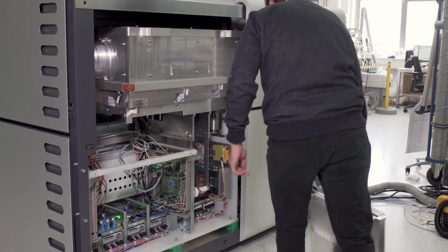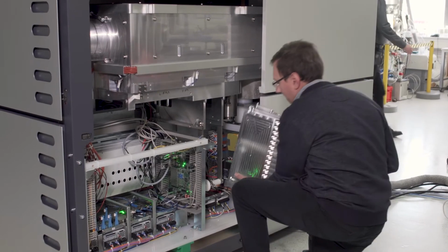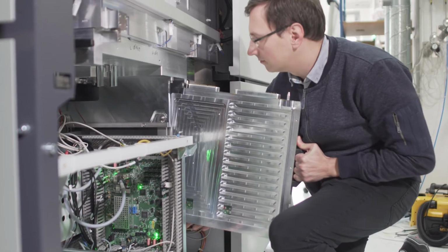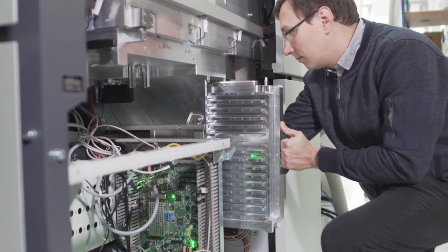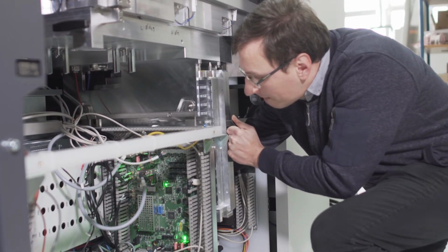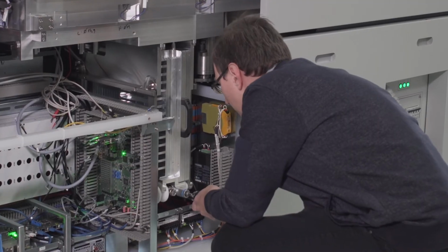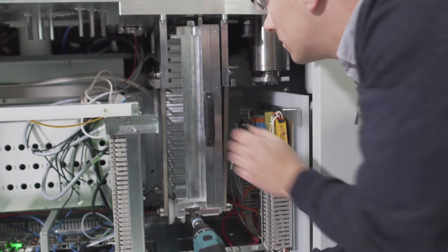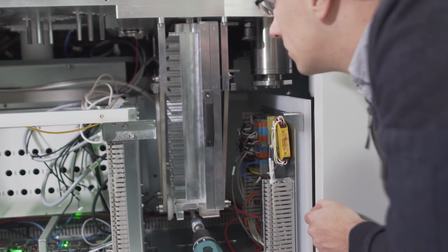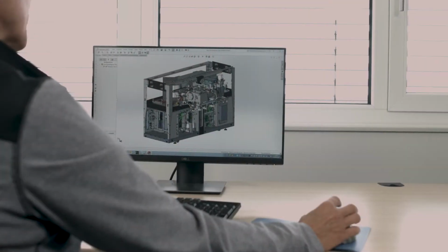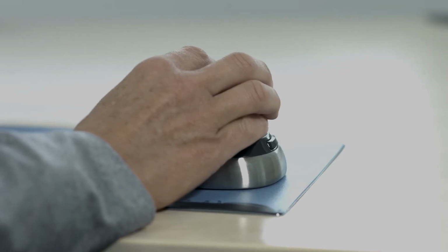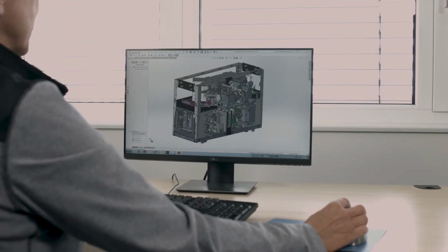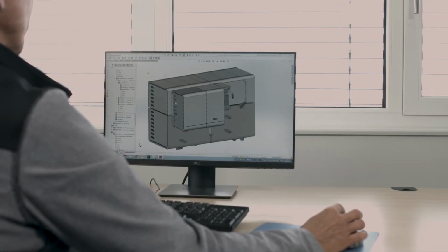The new ion current amplifier system allows the installation of 24 amplifier slots with automated gain calibration. It has a very compact design and is easy to service. Heated and maintained under vacuum, allowing lowest noise and highest stability. The new amplifier design incorporates an increased dynamic range and optimized time response. Every part of the Neoma Multi-Collector ICP-MS has been completely designed using specialized 3D software to improve visualization and ensure uniformity and compatibility early in the design phase.